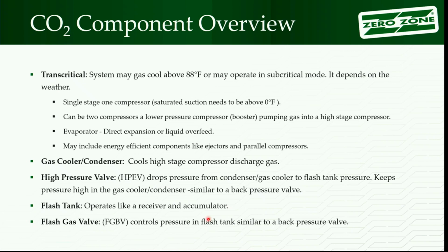just to make sure we all have the same basic background on CO2 components. Maybe you've heard it once or twice, but hearing it three or four times hopefully drives it in, so that you really get a good feel for it and are comfortable with it. We hear the term transcritical, and it only tells us one real thing about the system design: that it's going to go above 88 degrees and it will not condense. So that's the big thing.